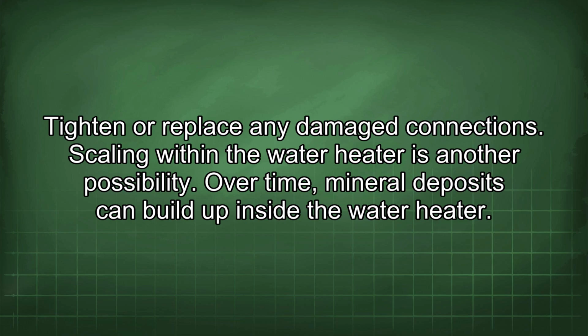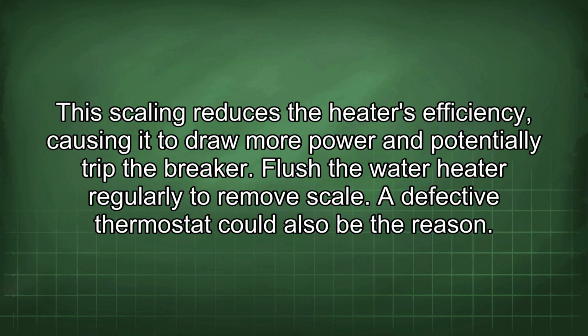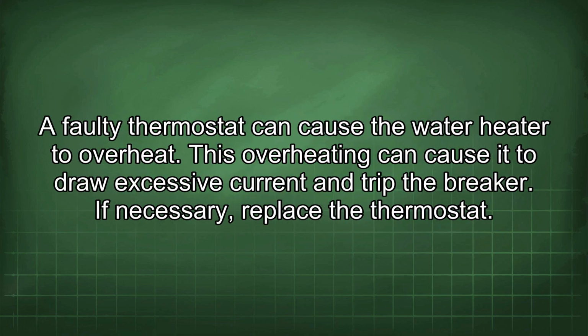Scaling within the water heater is another possibility. Over time, mineral deposits can build up inside the water heater. This scaling reduces the heater's efficiency, causing it to draw more power and potentially trip the breaker. Flush the water heater regularly to remove scale. A defective thermostat could also be the reason. A faulty thermostat can cause the water heater to overheat. This overheating can cause it to draw excessive current and trip the breaker. If necessary, replace the thermostat.